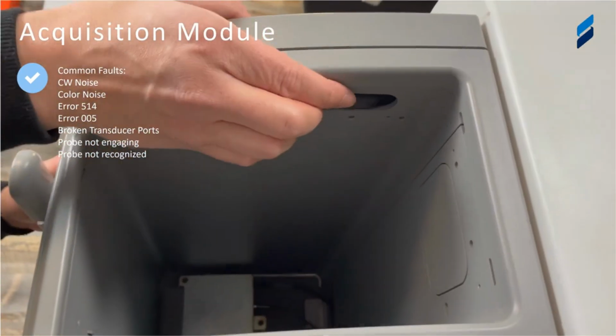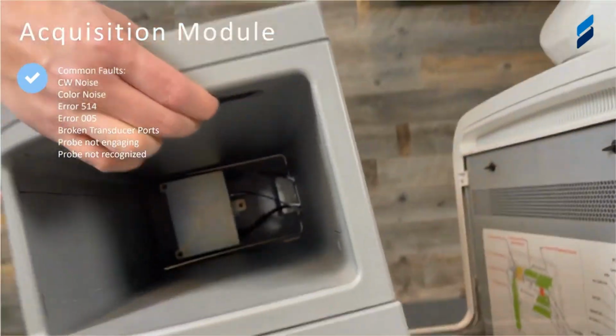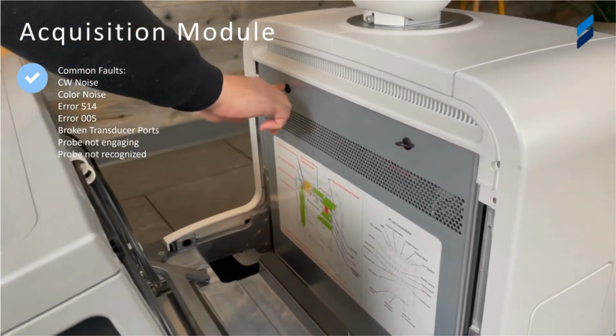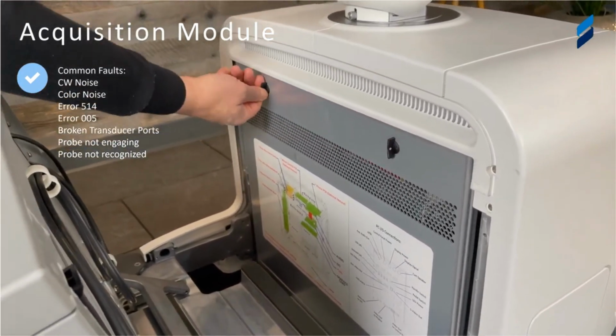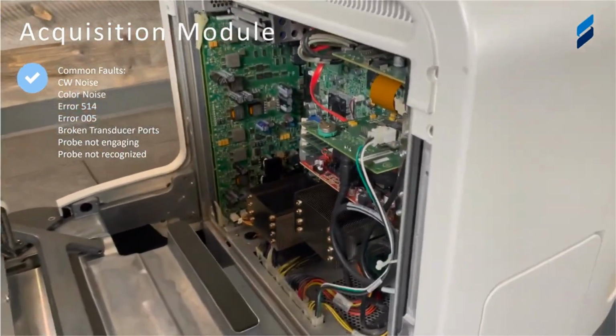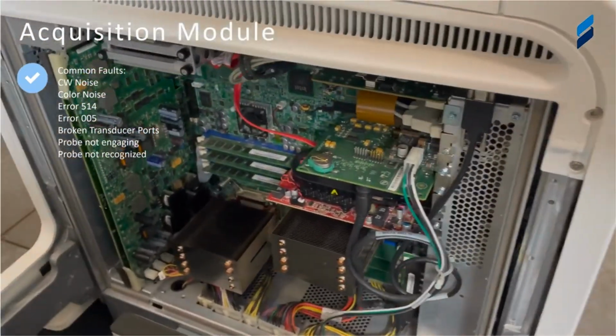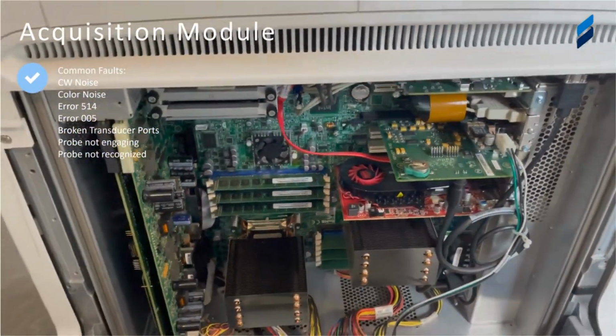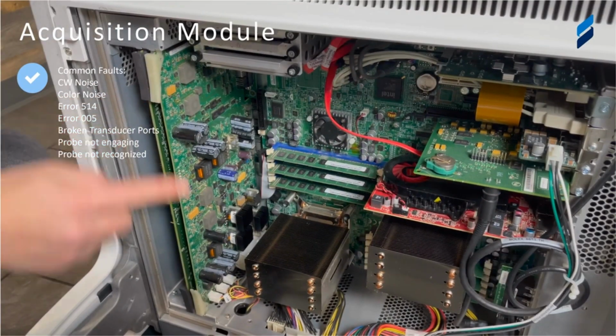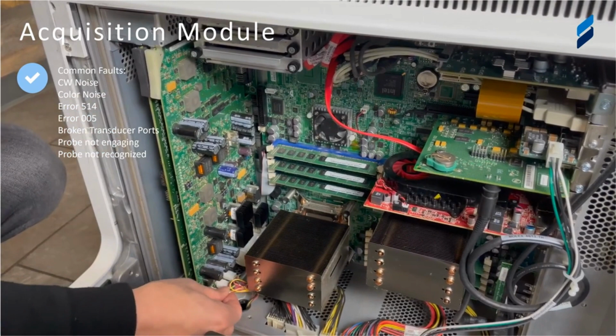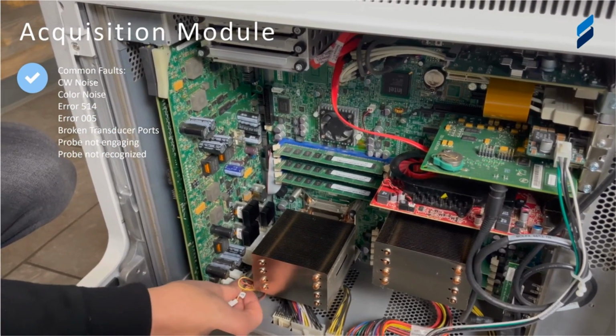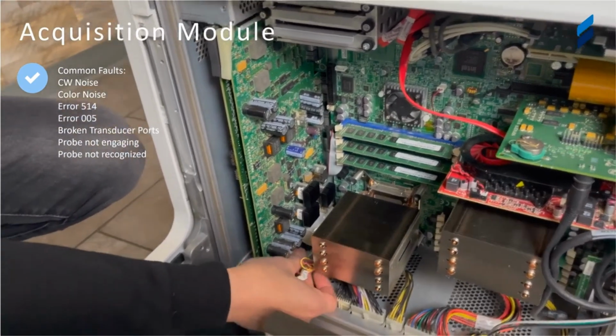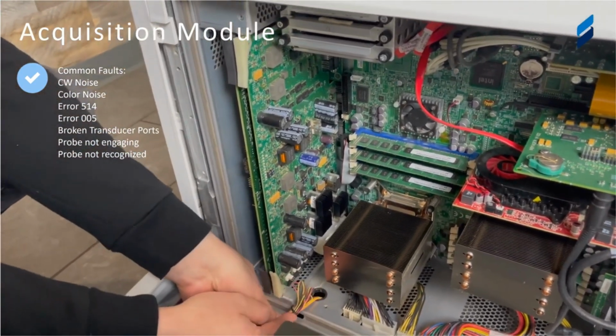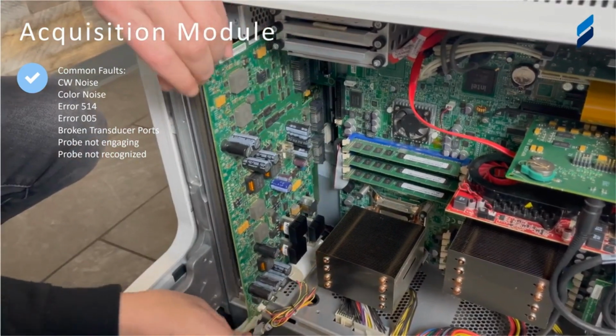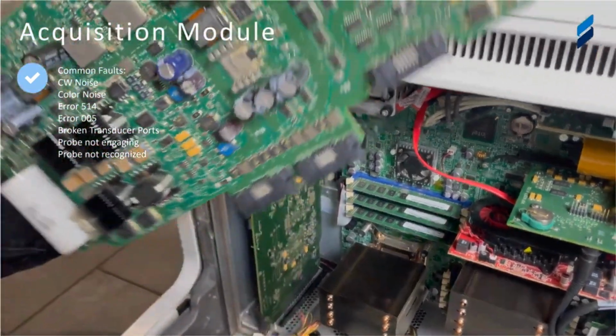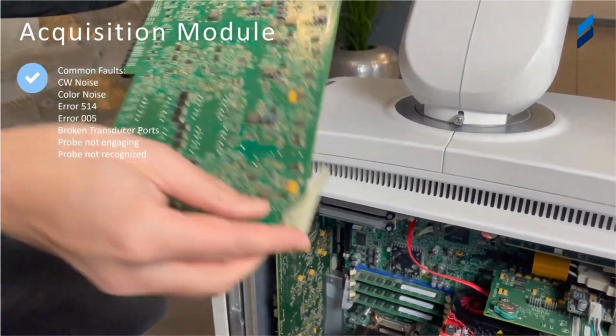So what we're going to do here is remove the power module because we are going to get access to the entire e-box and acquisition module assembly. Note, there are some quicker ways of doing this, but we're going to show you the safest way to get the equipment out to prevent damage from occurring. So we're going to remove the entire e-box and acquisition module assembly and then remove the acquisition module from there. We're taking you through the process of disassembly as if you are brand new and really trying to prevent any accidental damage along the way.